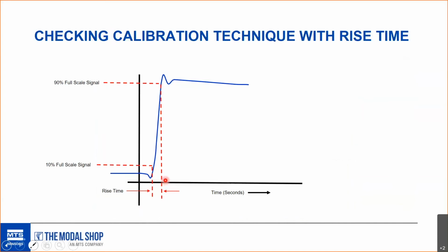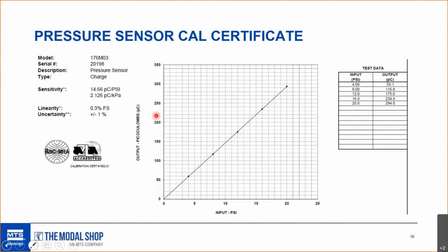And the rise time is just the time it takes for the signal to get from the 10% full scale value to up here at the 90% full scale value. So we take this data and compile it into a CalCERT, and these are the various components of it. Again, I'm beating to death here the diagonal nature of the curve. We have a data table over here of the data points that we collected up through 20 psi, and we calculate the sensitivity in picocoulombs per psi, the linearity as a percentage, and the uncertainty, which you'll see on CalCERTs. That's not a characteristic of the sensor.